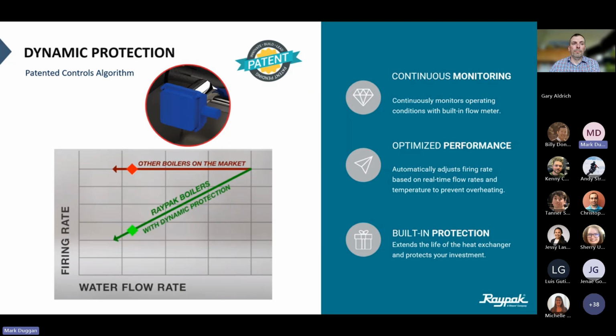So next we'll talk about our dynamic protection. I've mentioned it a couple times here, but basically there's this blue flow meter. It's an electromagnetic flow meter that sits on the inlet side of the boiler. So it's constantly monitoring flow to that boiler, and it adjusts the firing rate accordingly. We've got different flow rates we need to meet depending on the size of the heat exchanger. Obviously a 1 million BTU is going to need less flow than a 4 million BTU, but we've got those parameters we need to meet built into the control.